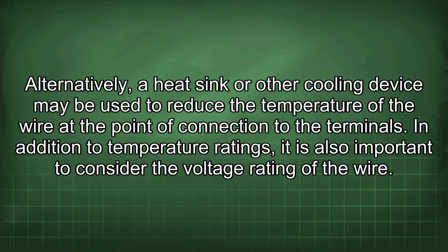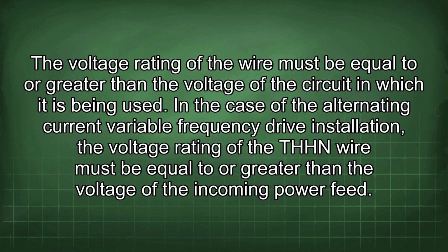In addition to temperature ratings, it is also important to consider the voltage rating of the wire. The voltage rating of the wire must be equal to or greater than the voltage of the circuit in which it is being used. In the case of the alternating current variable frequency drive installation, the voltage rating of the THHN wire must be equal to or greater than the voltage of the incoming power feed.